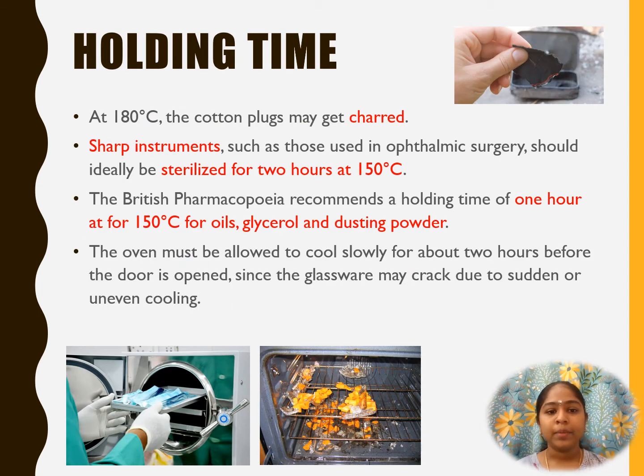Specific holding time. At 180 degrees, the cotton plugs may get charred. Sharp instruments like instruments used in the ophthalmic surgery must be sterilized for 2 hours at 150 degrees Celsius. The British Pharmacopoeia recommends a holding time of 1 hour at 150 degrees Celsius for oils, grease, etc. The oven must be allowed to cool for at least 1 to 2 hours before opening the door, since the glassware may crack due to sudden or uneven cooling.